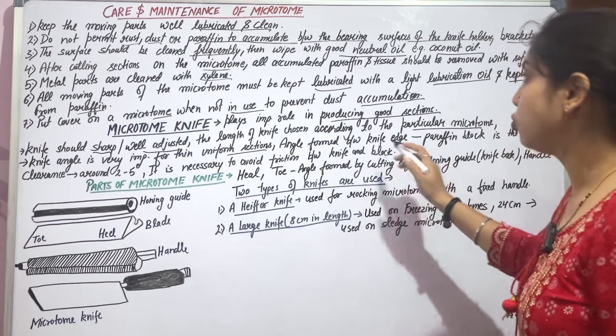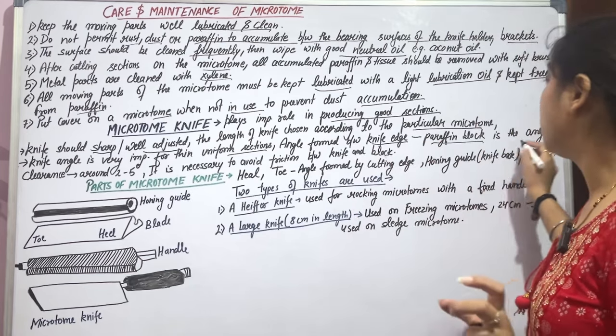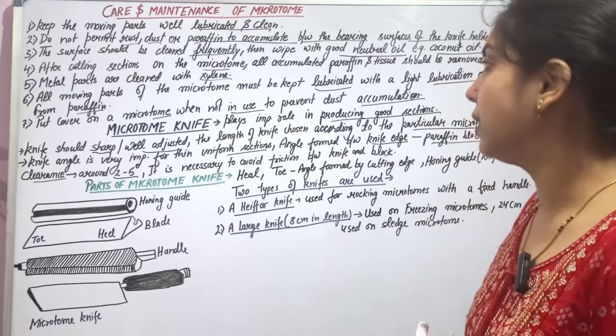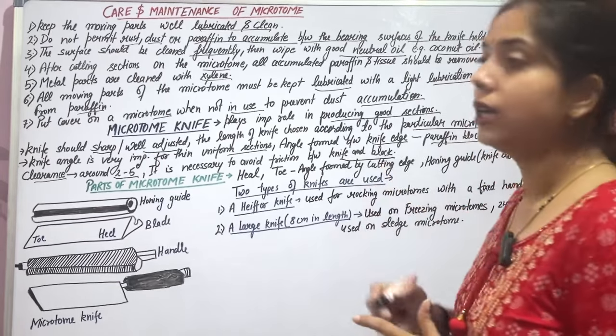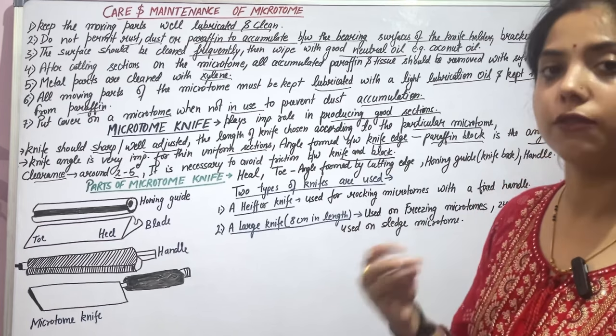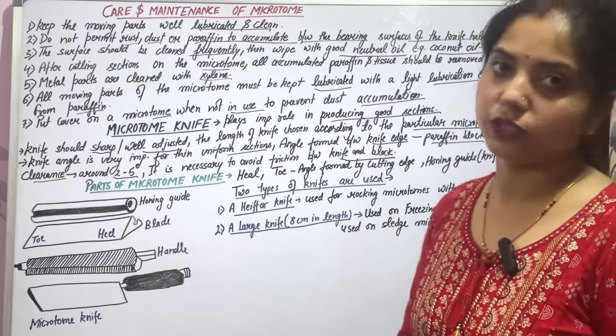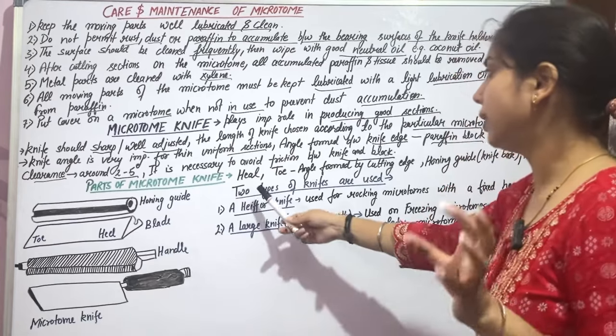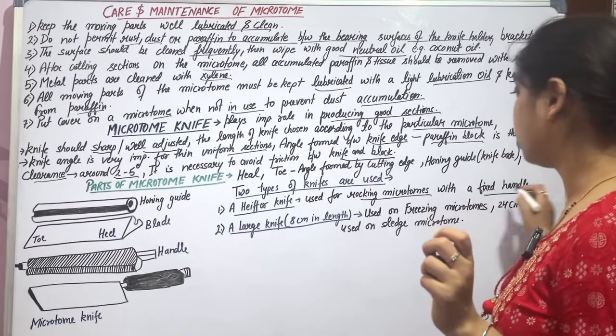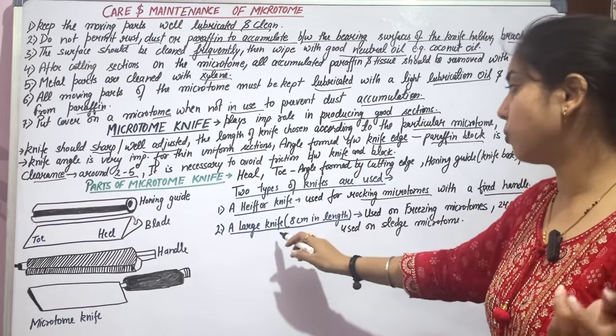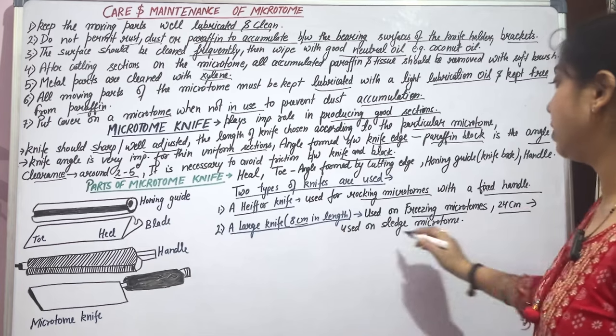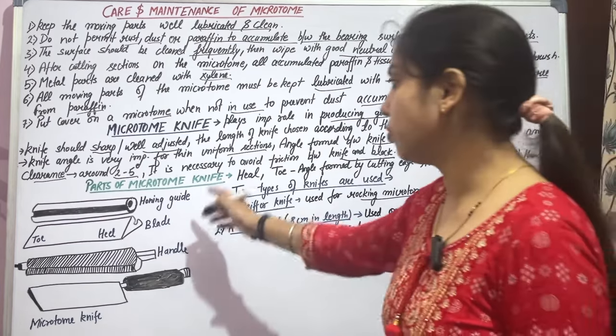The angle formed between the knife edge and the paraffin block is called the angle of clearance, which is 2 to 5 degrees. It is necessary to avoid friction between the knife and block for smooth serial section cutting. There are two main knife sizes: a smaller knife used for the rocking microtome, and a larger knife of 8 cm used for the freezing microtome, while the base sledge microtome uses a 24 cm knife.